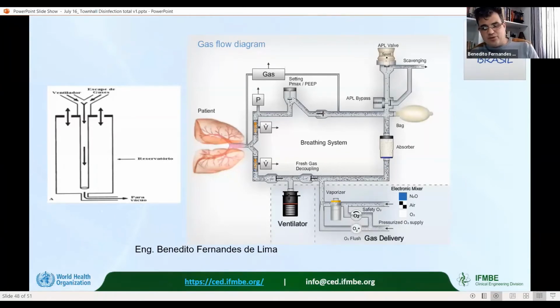Relating to soda lime, known as carbon dioxide absorber, it was necessary to change the disposal process. It became infectious biological waste. Before, it was considered corrosive waste. This way, it is necessary to use personal protective equipment, or PPE, to avoid biological contamination. Before the coronavirus pandemic, we used to sterilize when the equipment was used with infectious respiratory diseases. When the coronavirus pandemic started, it was necessary to create new protocols to process these items at the sterilization central.